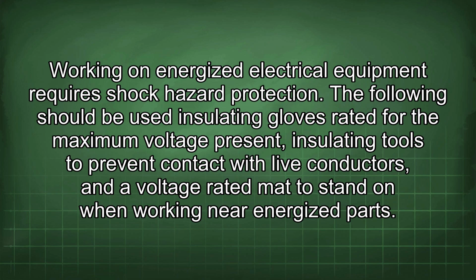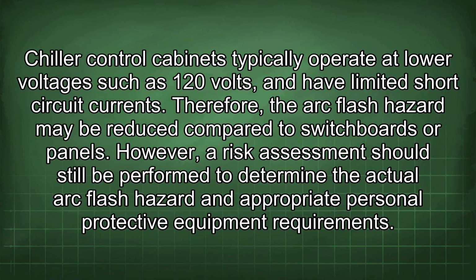Working on energized electrical equipment requires shock hazard protection. The following should be used: insulating gloves rated for the maximum voltage present, insulating tools to prevent contact with live conductors, and a voltage rated mat to stand on when working near energized parts. Chiller control cabinets typically operate at lower voltages such as 120 volts and have limited short circuit currents. Therefore, the arc flash hazard may be reduced compared to switchboards or panels.